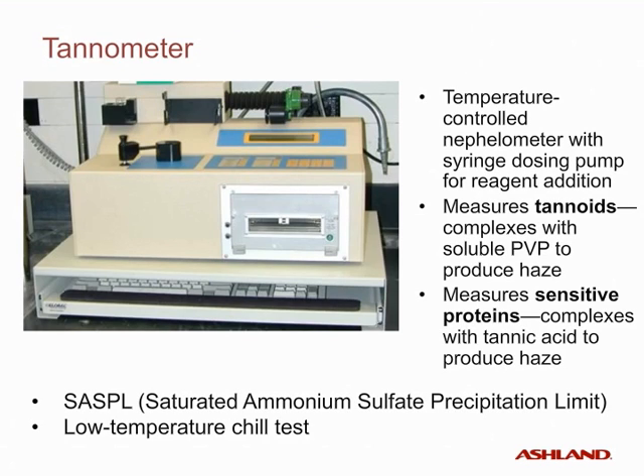The tannometer instrument allows a variety of measurements for haze precursors. It is a temperature-controlled nephelometer with a syringe dosing pump for adding various reagents depending upon what is being measured. When tannoids are measured, we use a soluble PVP that complexes readily with tannoids to produce haze; the amount of haze that develops can be equated to a concentration of tannoids in the beer sample. The instrument also measures sensitive proteins using a solution of tannic acid, which selectively precipitates the proteins most reactive with tannic acid. The amount of haze that develops is indicative of the quantity of haze-forming proteins in the beer sample.